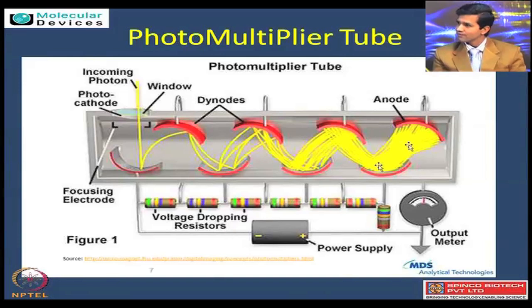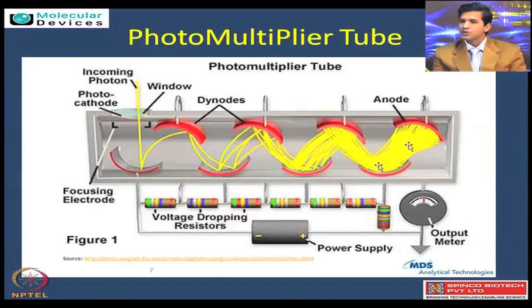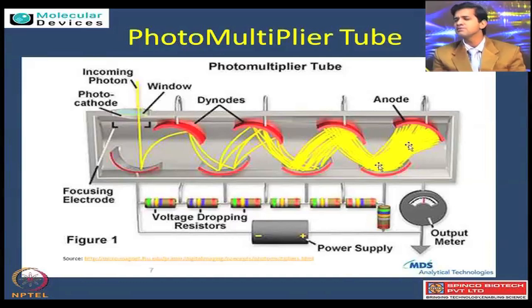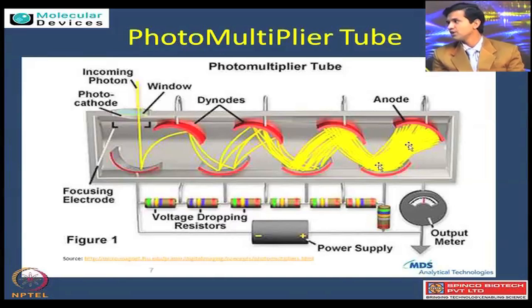When people scan these microarray slides it always asks for the PMT gain - that is the photomultiplier tube gain. The basic rule is that in any scanning you do not want to see a white spot. A white spot essentially means saturation, and to avoid saturation - with exceptional cases for a few controls - people avoid that happening. The PMT actually ranges from something like 300 to 700 which helps one control how much photon multiplication can be done, so the lowest can also be seen and the highest does not become saturated.